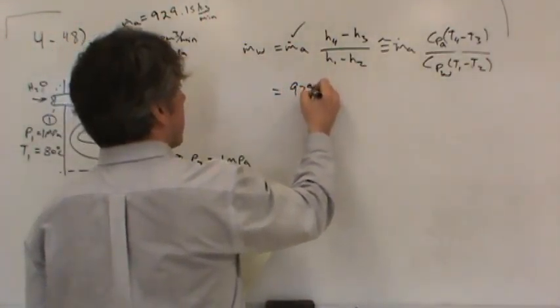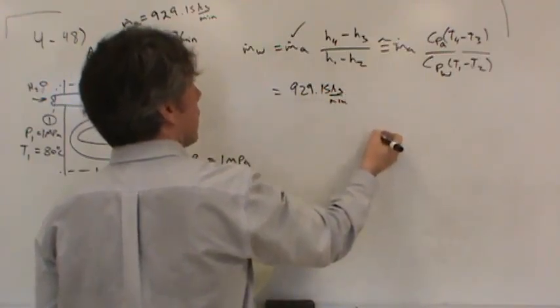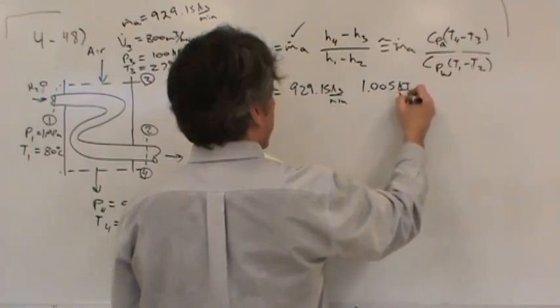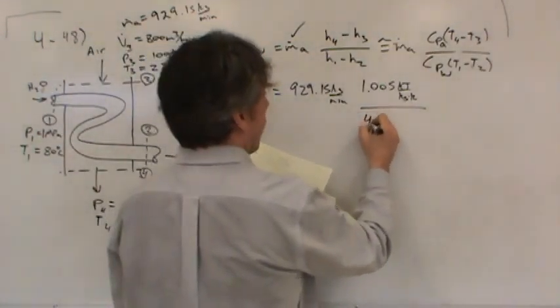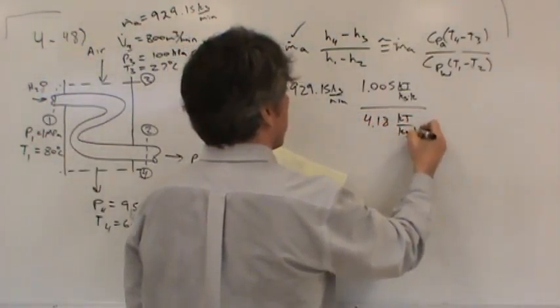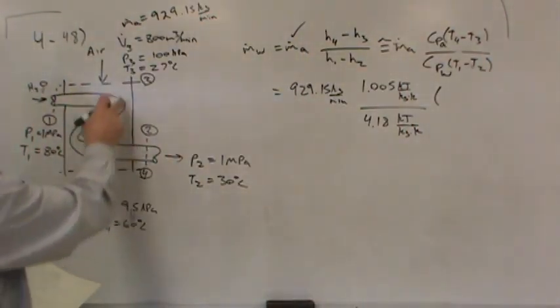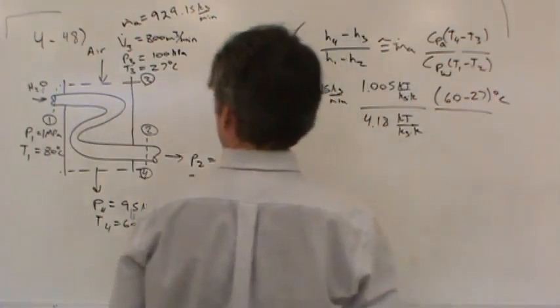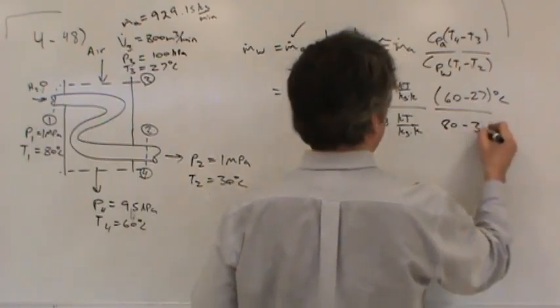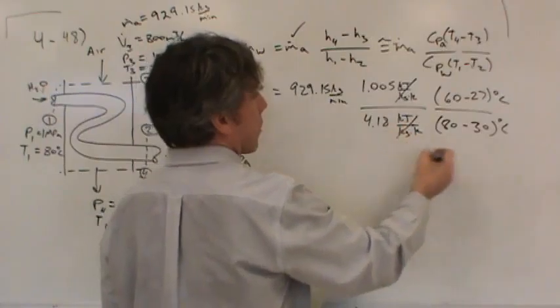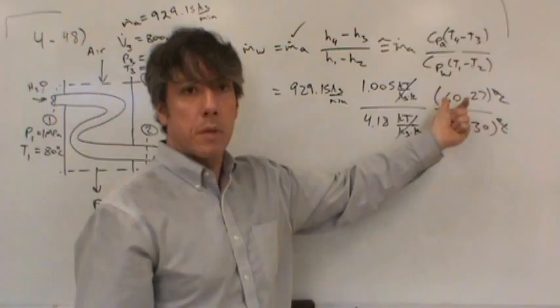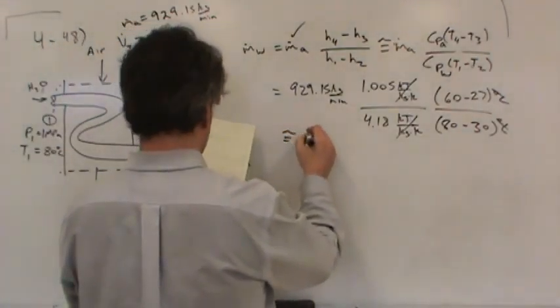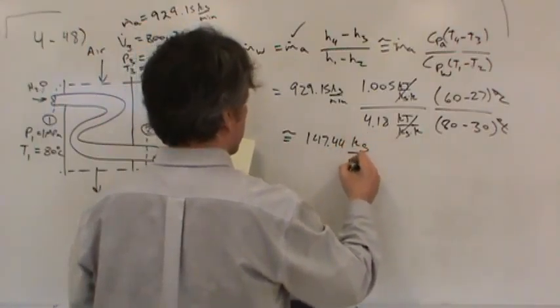So let's see what happens. Well, the mass flow rate of the air, again, 929.15 kilograms per minute. The heat capacity of air, if you don't know it right off, it's in table A2. The heat capacity of the air is 1.005 kilojoules per kilogram per kelvin. The heat capacity of water is about 4.18 kilojoules per kilogram per kelvin. The temperature change, T4 less T3 would be 60 less 27. That's degrees Celsius, of course. The temperature change of the water, T1, 80, less T2, 30. Notice the kilojoules per kilogram per kelvin go away. The degrees Celsius go away. Did I make a mistake? Should I have used kelvin for these temperatures? It doesn't matter. It's just a difference. That's right. Good job. So the mass flow rate of the water, then, comes out to about 147.44 kilograms per minute.